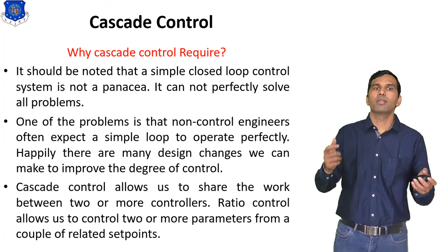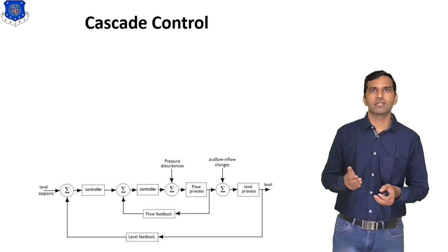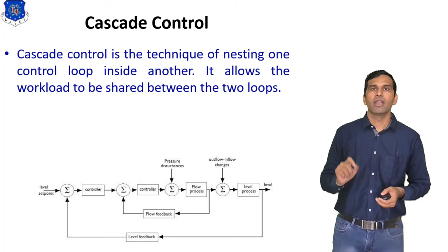So this is the simple block diagram of the cascade control system. You can see here we use two controllers. Why do we use two controllers? As the name suggests, cascade means a series connection of two controllers. So cascade control is the technique of nesting one control loop inside another. You can see in this diagram, the first one is the big control loop, and inside that control loop you can see the second control loop. It allows the workload to be shared between the two loops.